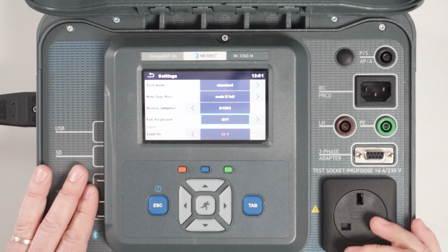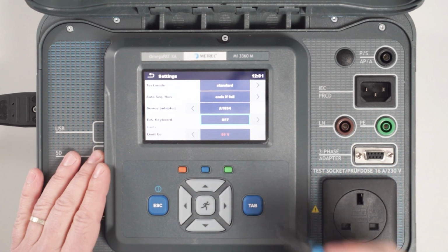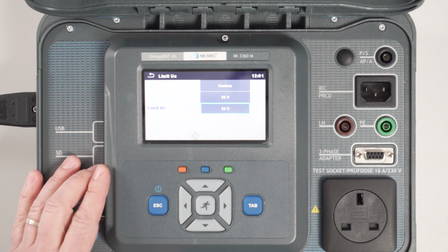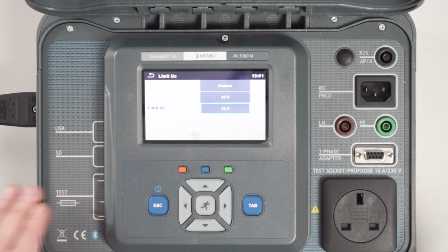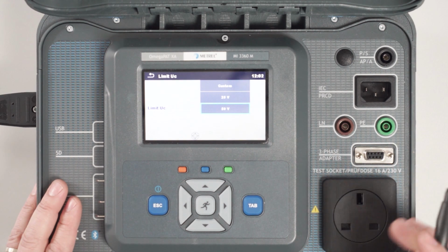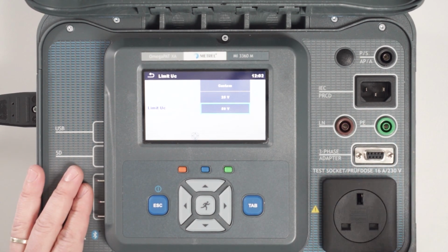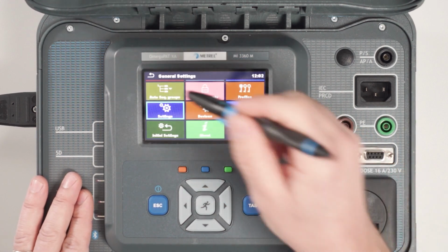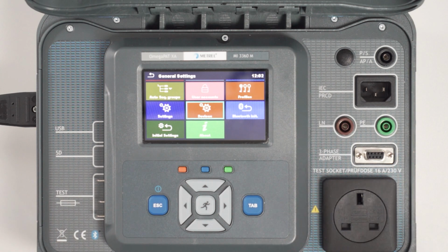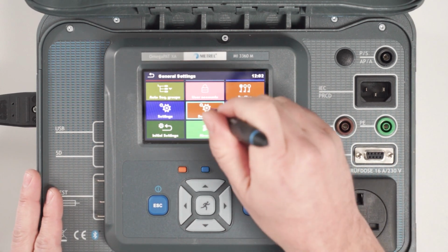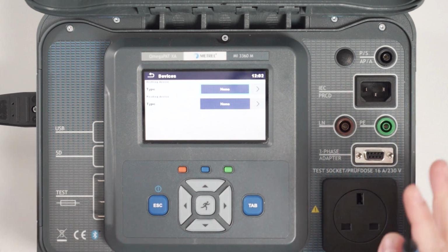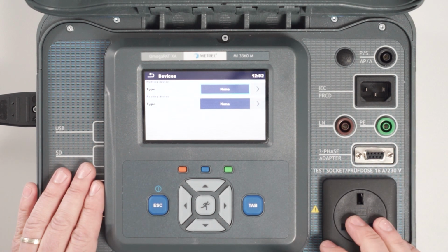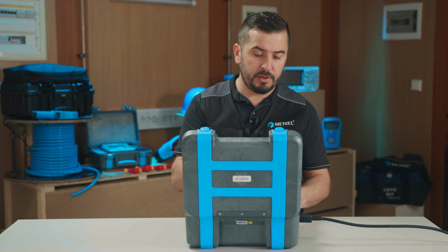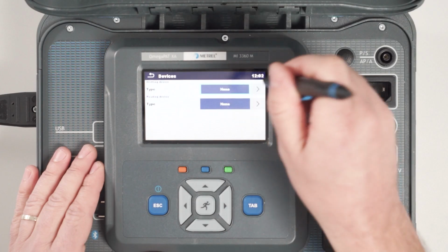And we have also the limit for the contact voltage, which can be changed here, depending on the environment we are in, and this is strictly related to the measurements of the RCDs. So this is about the settings menu. Then we have here additional menu called devices. Inside this devices menu, we have option to set writing devices or to set reading devices.